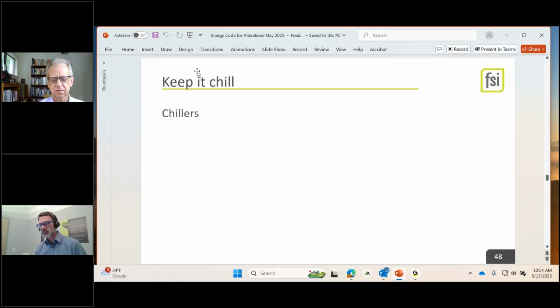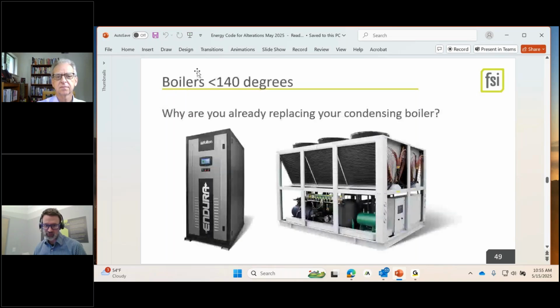Chillers. Heat recovery chillers are just now getting their act together enough that we've got industry standard ratings, so you can make medium temperature water in place of what is normally 180-degree boiler water, where you're required to use a heat pump, as Duane talked about. It is coming together though, and literally last week I got my new lowest temperature operation, minus 20 degrees, and the last time we did this presentation, it was 12 degrees, 2 years ago. So it is coming along nicely as an industry. There are new products every month.